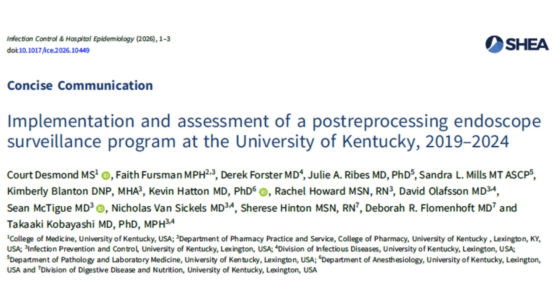And the surprises don't stop there. The EUS scopes, the ones with the ultrasound probes attached, had the highest actual match rate in the study. Match rate meaning? Out of 3 positive cultures for EUS scopes, 1 was an exact match, meaning the organism they found surviving on the scope exactly matched the superbug of the previous patient. That is a 33.3% match rate. Wow. And just to round out the data, the standard colonoscopes had a low 5.1% positivity rate and 0 matches.